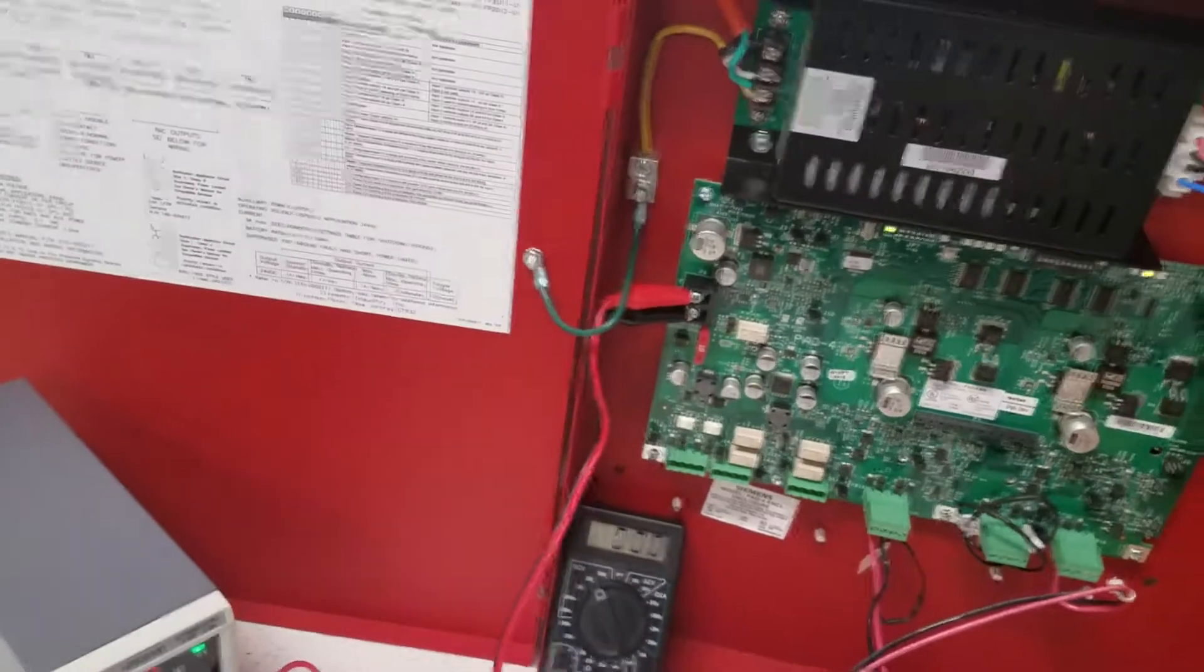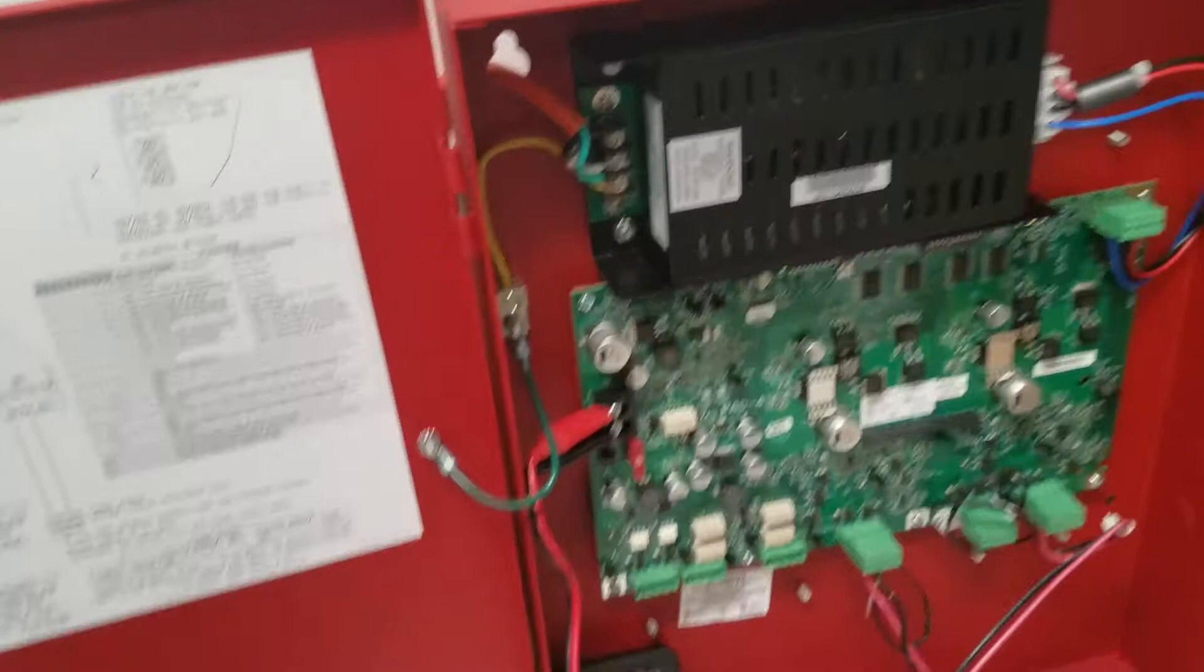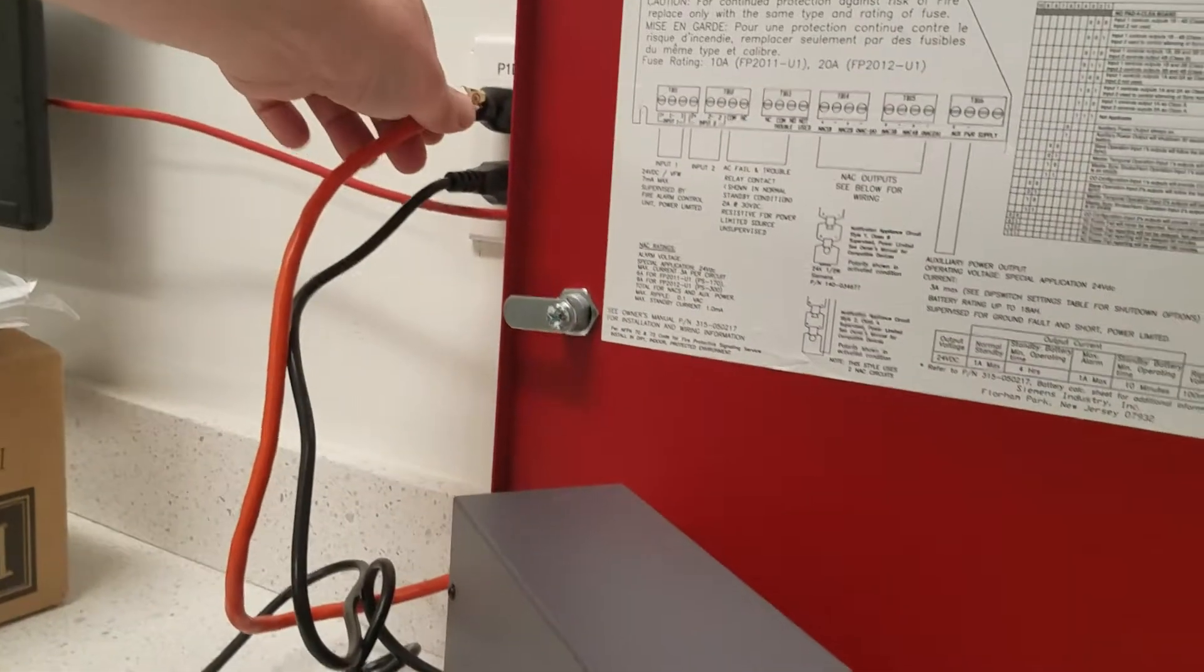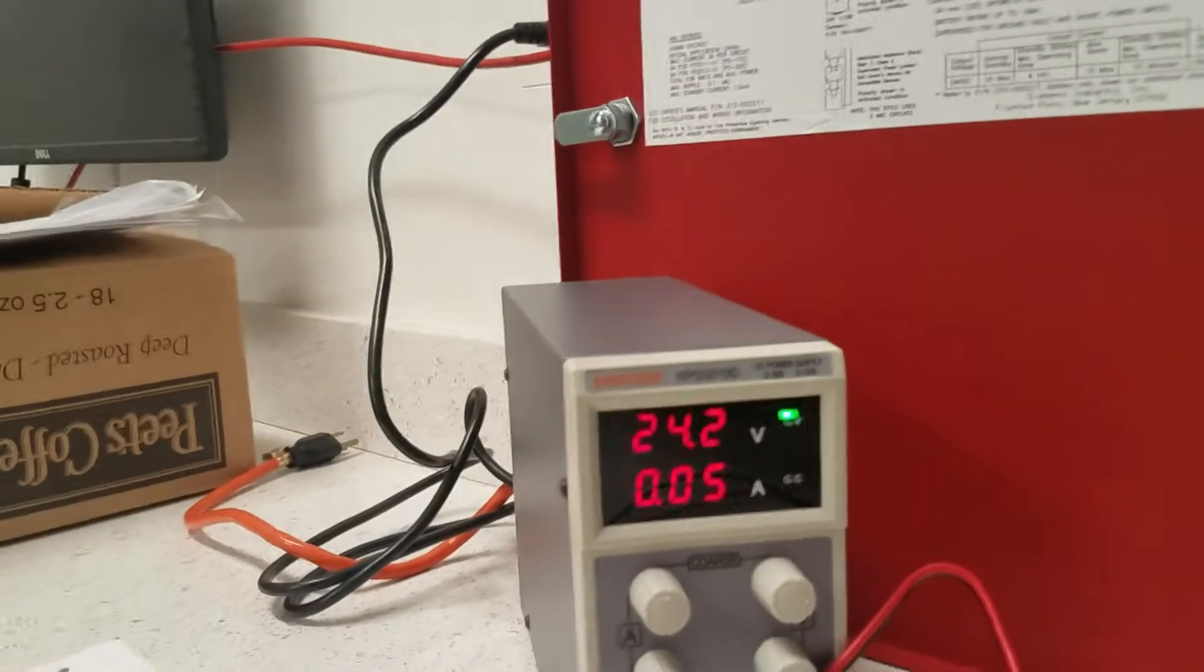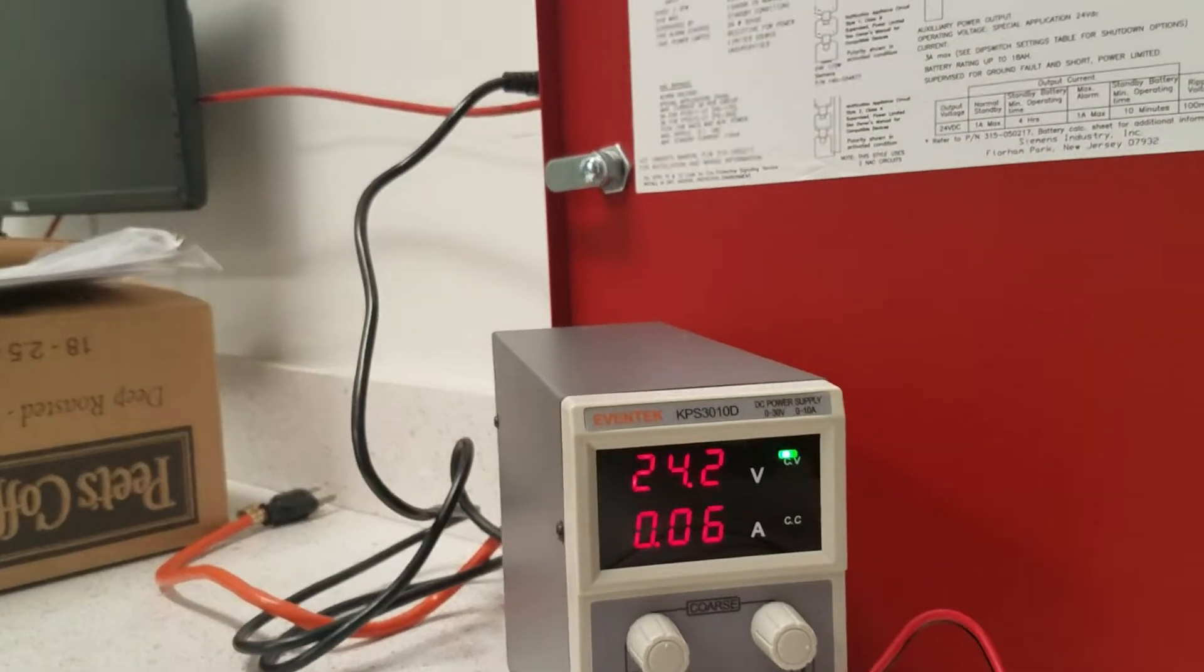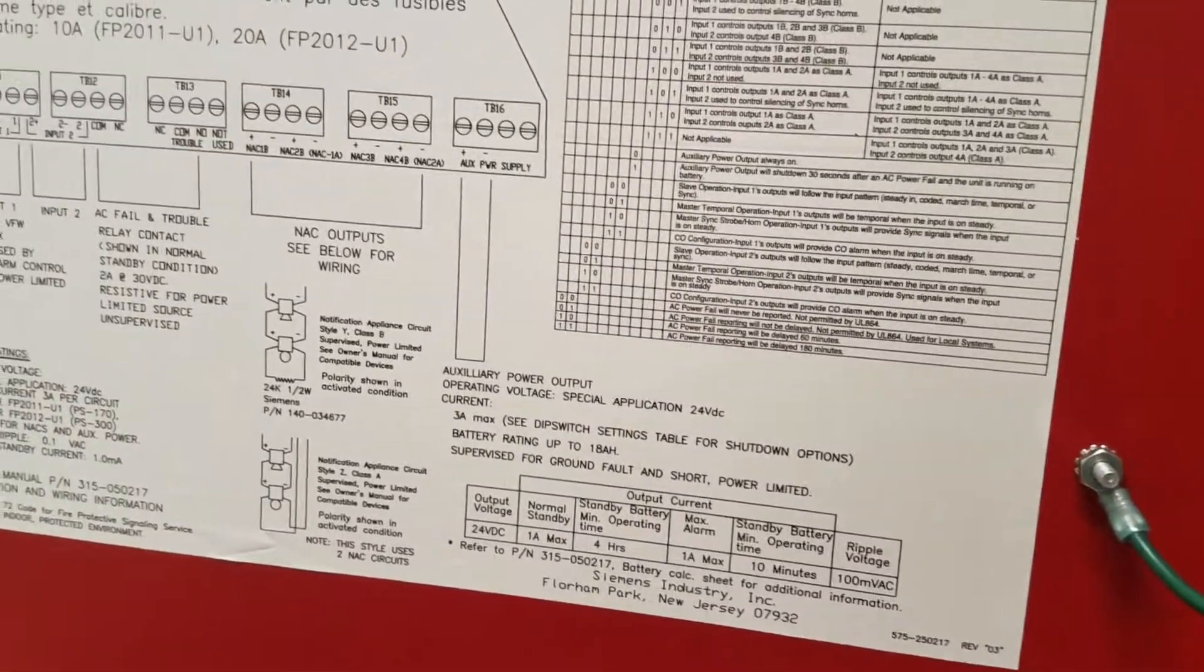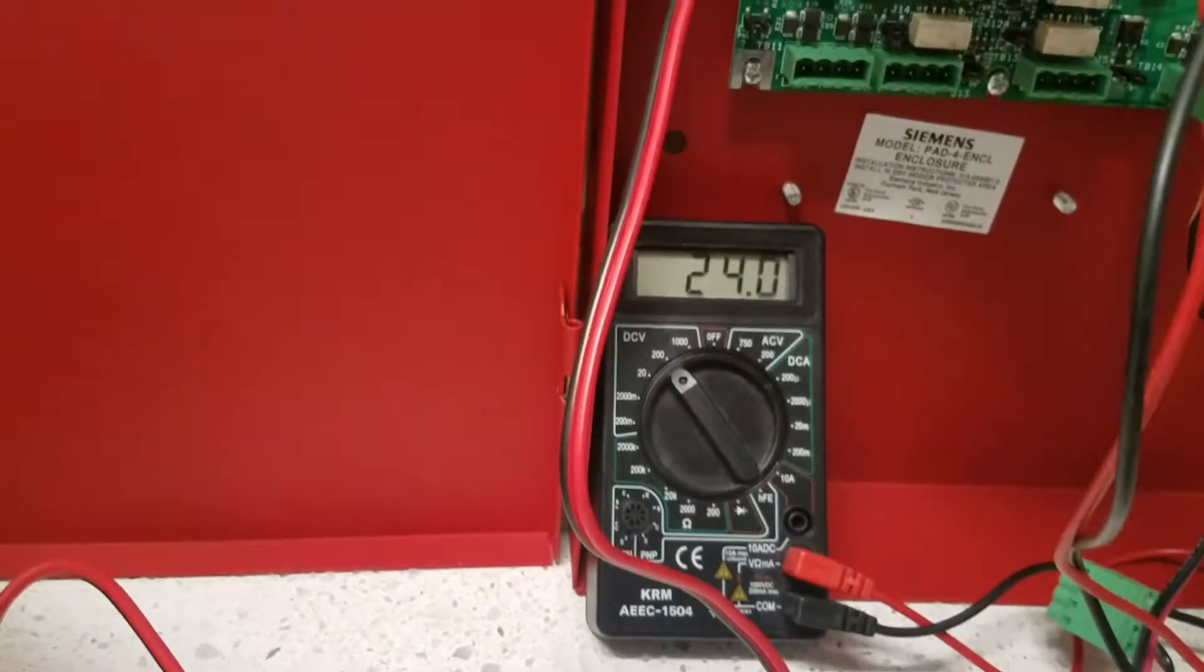Now what I want to simulate is a 120 power loss. So if you take a look and watch the variable meter as I go through and I unplug the power supply, the 120 volts, it now registers that it is giving 0.06 amps at 24 volts. As we measure before and we can measure again, it is giving 24 volts.